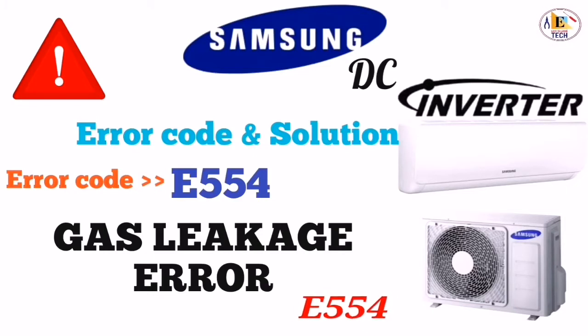First of all, you check the position of your indoor evaporator in sensor, if it is normal or not. If it is not placed in the normal place, place it in the normal place and start the unit. And if your unit starts, it means there was an issue with the in sensor of the evaporator. And if it doesn't start and again shows the error for the gas leakage, then you have to check the EEV valve operation. Put the power on again and listen for the sound of your EEV valve. If there is no sound, it means your EEV valve is faulty. Then you have to replace your EEV valve.